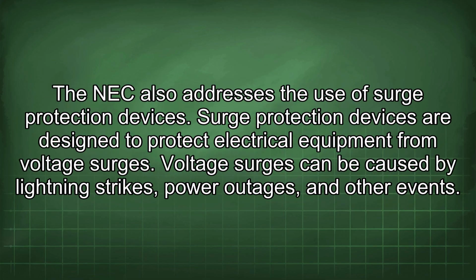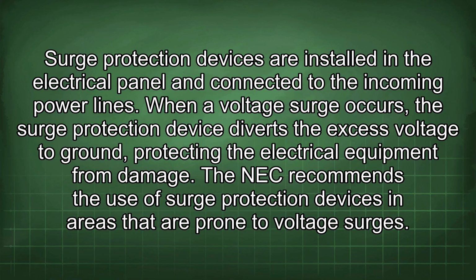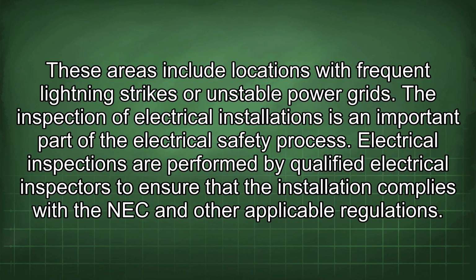The NEC also addresses the use of surge protection devices. Surge protection devices are designed to protect electrical equipment from voltage surges. Voltage surges can be caused by lightning strikes, power outages, and other events. Surge protection devices are installed in the electrical panel and connected to the incoming power lines. When a voltage surge occurs, the surge protection device diverts the excess voltage to ground, protecting the electrical equipment from damage. The NEC recommends the use of surge protection devices in areas that are prone to voltage surges. These areas include locations with frequent lightning strikes or unstable power grids.